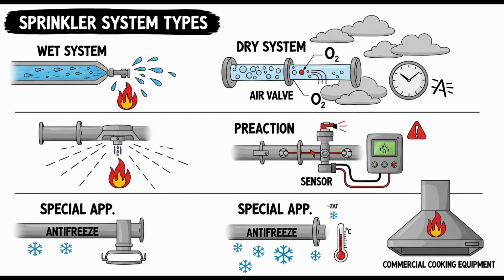Okay. Correct. A drain test connection is required at the most remote point of any antifreeze system. For larger systems, over 150 gallons, an additional test connection is needed for every additional 150 gallons of volume. Why multiple test points on large systems? This allows for easier draining of the system for solution replacement or maintenance, and also provides points to draw samples for testing the antifreeze solution concentration and condition over time. Makes sense.